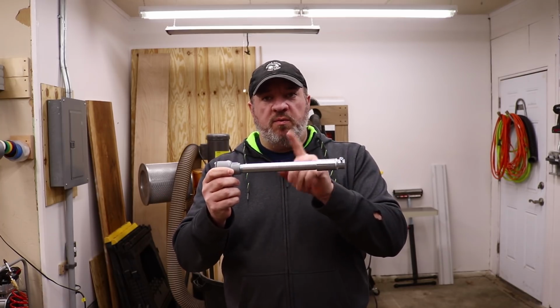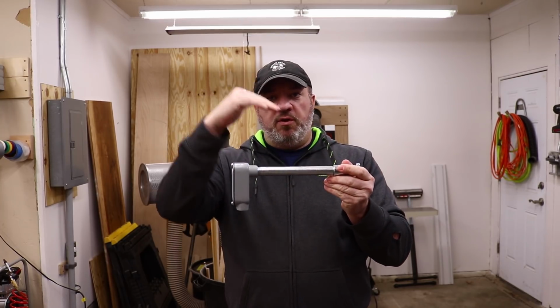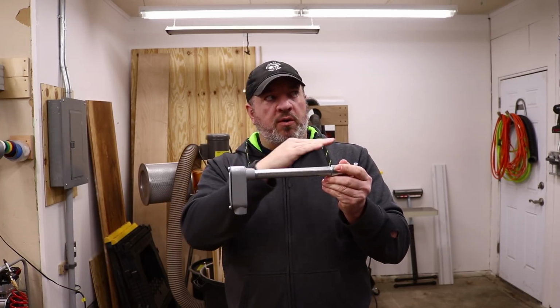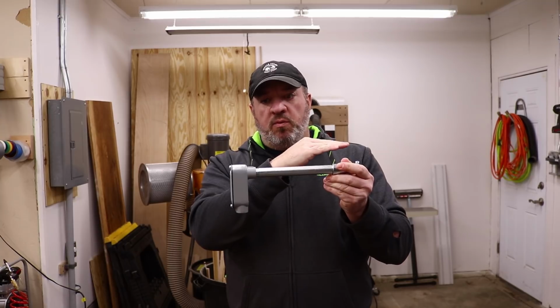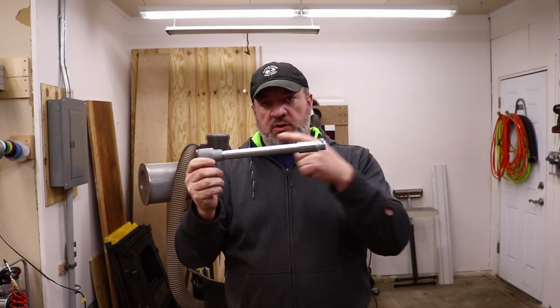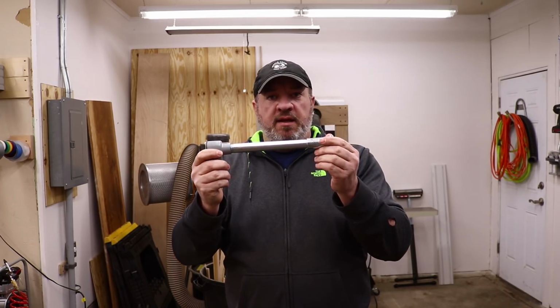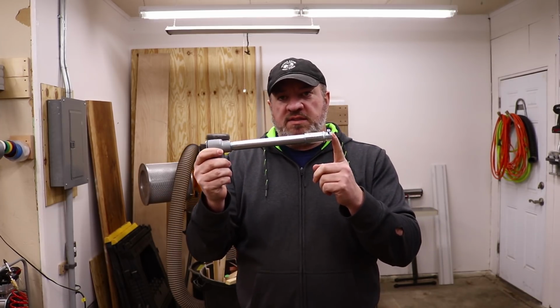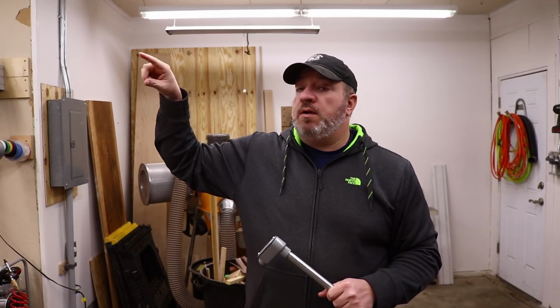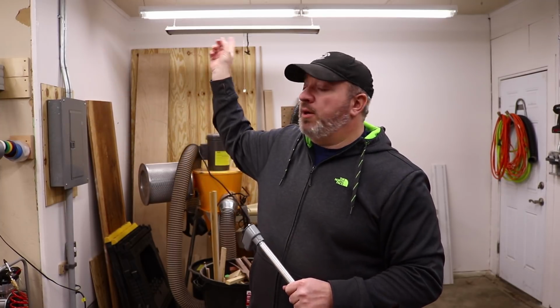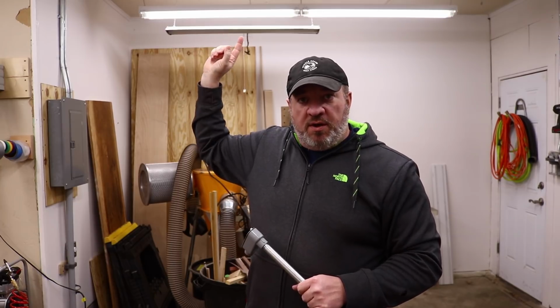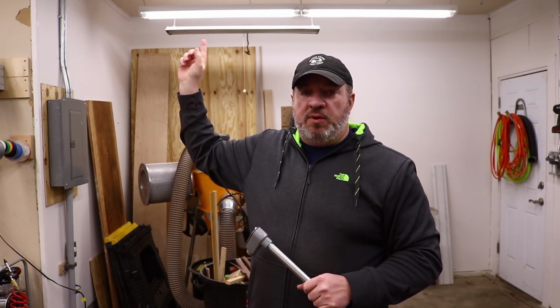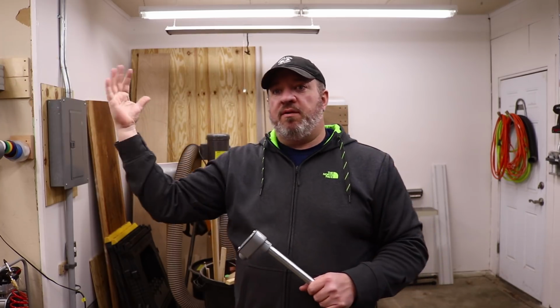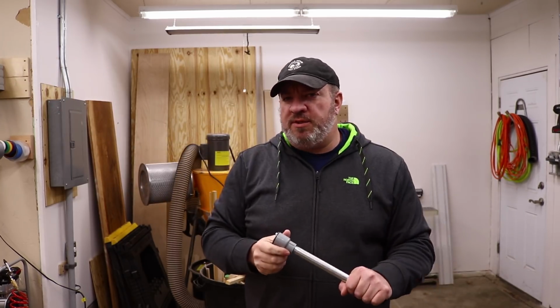Also, because of the way my ceiling works, I have to do a little bit of an offset to get it down to where it can get below the framing and actually make it through the wall and outside. So this was the easiest thing to do. I can drill a hole, send this through from the outside, and then connect the EMT on the inside of the house. Because of the way I ran the EMT in here when I installed my sub panel and upgraded all the lighting and electrical in here, I've got to jump over a few conduit runs already on the ceiling. It was bad planning on my part, but I thought most of the stuff I was going to be adding to the shop was going to be this way rather than, you know, back and this way. So that's going to be a little bit tricky with the bending. All right, let's do some electrical.